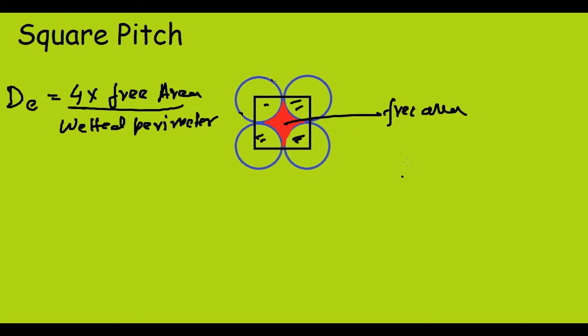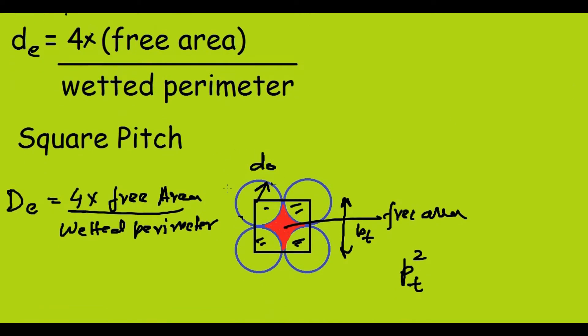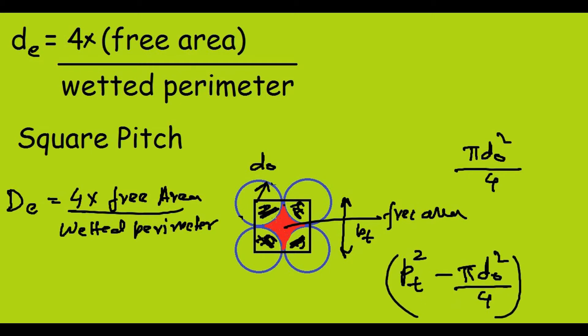The area of this square is Pt squared, because the side is the tube pitch Pt. The radius of these circles is DO. Adding 4 quarter circles gives one full circle, so we subtract πDO²/4. This gives the free area as Pt² − πDO²/4, which is the area of this red shaded portion.